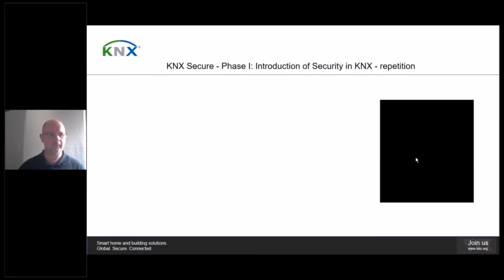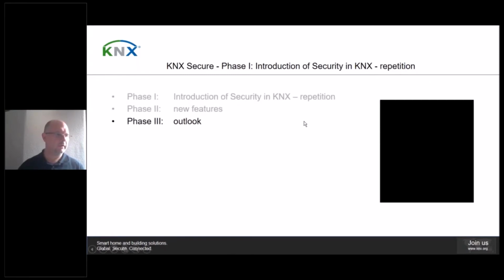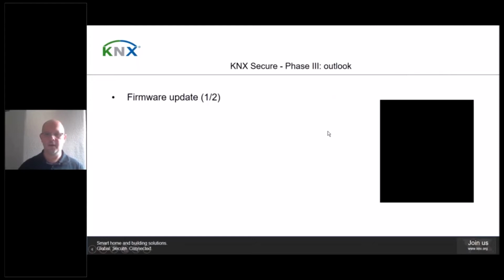Outlook to the future. That's the third phase of my conference presentation. First of all, the firmware update. What's the goal? The goal is to allow a firmware update in the installed KNX devices. This can be a small patch, a replacement of a routine, or a complete update of the device's KNX stack or even other functionality. What's the use case? The first use case would be to allow for the correction of security flaws. If it appears that the device has security weaknesses in its code, then firmware updates should allow that these get resolved, or an update of the security protocol.